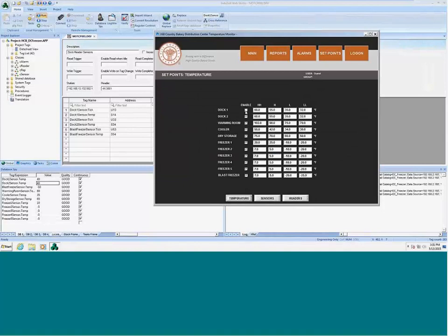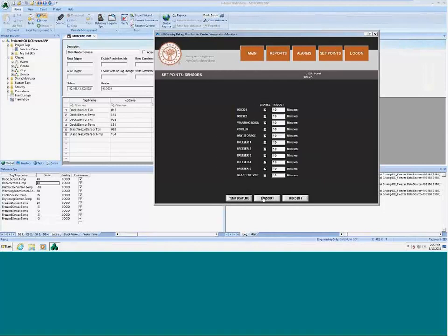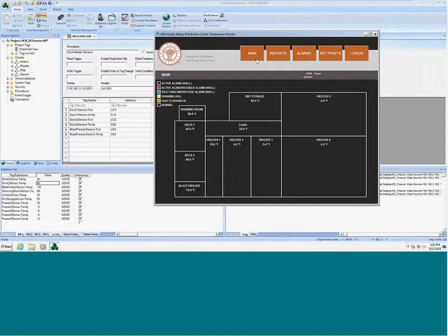We'll also have alarms set up for timeouts for each of the sensors and readers since we are dealing with wireless technology. The log-on button is to log in. I have the system tied into their Active Directory system, so the users throughout their company can just use their typical domain credentials to log in, get their rights that they should have, and then either be allowed to change set points, be blocked from that, be allowed to acknowledge faults, etc. So that's an overview of the runtime.